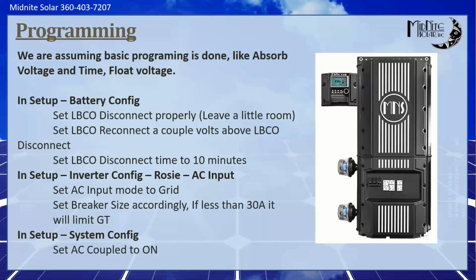But it asks you all that on startup. It walks you right through it, and then it goes to work. If you're doing closed loop, that stuff is not critical, because the closed loop commands everything to happen by default. But I recommend setting it anyway, because if somebody was to unplug a cable, or a mouse chews through the wire, whatever, the battery's BMS quits talking. I've seen that on a couple different brands of batteries. The system will default back to open loop and not just shut down. So it will give you a fault that there's BMS issues, but it won't leave you in the dark. It will keep running in an open loop environment. So setting those 3 or 4 settings is important.